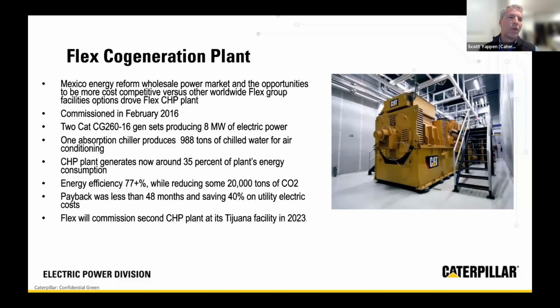So the customer is seeing something that they really wanted to see: a very reliable system delivering energy at a very high efficiency, low heat rate, with those engines at 43 to 45% on a lower heating value basis, in that ballpark. Very high electrical efficiency and delivering waste heat to energy for their cooling needs and baseload cooling needs of this facility, a 2 million square foot facility.